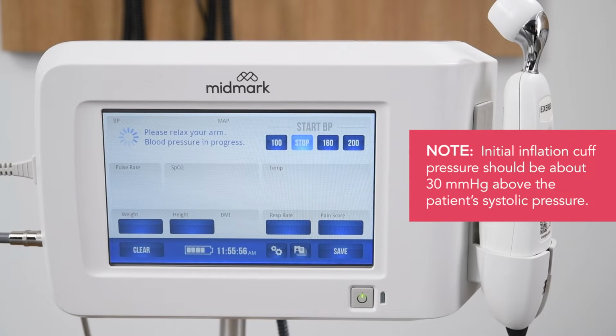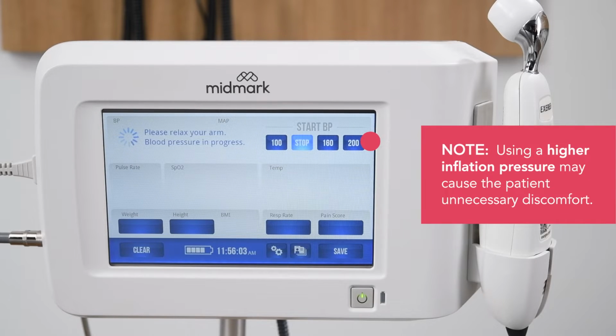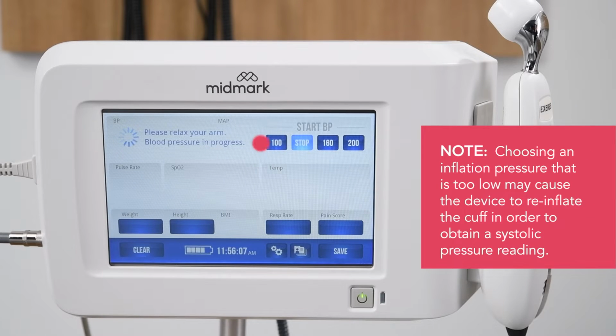Ideally, the initial inflation cuff pressure should be about 30 millimeters of mercury above the patient's systolic pressure. Using a higher inflation pressure may cause the patient unnecessary discomfort. Choosing an inflation pressure that is too low may cause the device to re-inflate the cuff in order to obtain a systolic pressure reading.